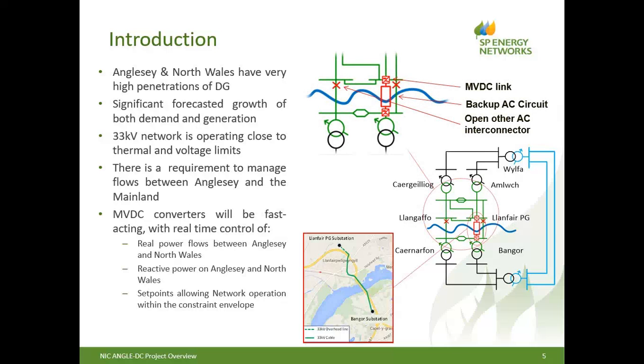So what you can see there is we've given you a bit more detail, but you can see that the 33 kV connections across to the island from the mainland are going to be supplemented by one of the existing circuits, which is a double circuit between Llanfair PG and Bangor, and that's the one we're going to turn into the DC link. It's a little bit unique in as much as it is a double circuit, and it goes cable to cable to both ends, and it's literally just bunched on the breaker, and that gives us the opportunity to turn each discrete cable circuit into a pole of the DC link.